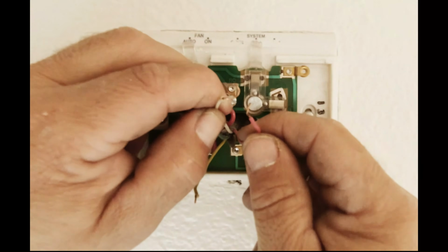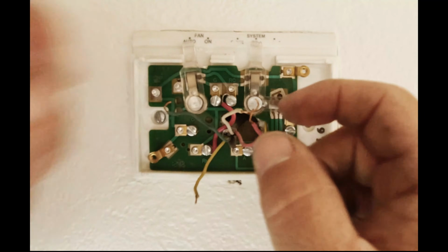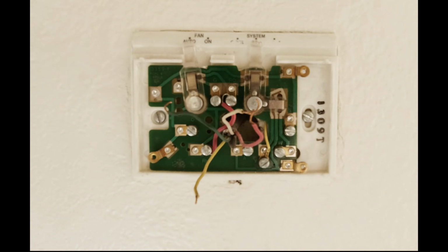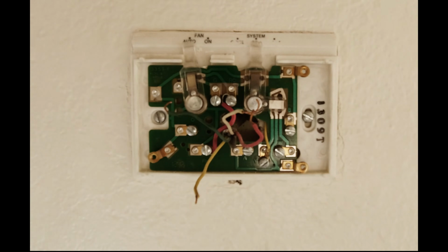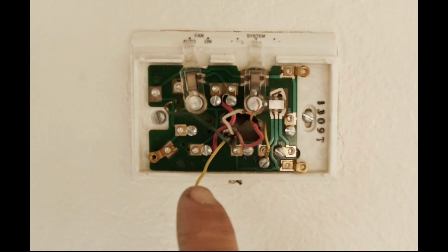Now, the white is always going to be the heater. Once you connect the heater over to the 24 volts, or the red, the heater's not going to kick on right away. It'll take about 3 minutes usually, especially if it's a package unit. Sometimes you'll hear the fan start blowing cold air, and you're thinking, man, this thing's not warming up. Well, it'll take a few minutes. There's a process up there: the inducer and different things have to kick on, then the flames. So if you feel cold air at first, that's totally normal. It's got nothing to do with the compressor. That's the way these units run.